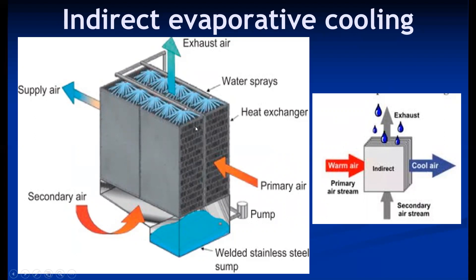In indirect evaporative cooling, since there is no direct contact between primary air and water, no absolute moisture is added to the air — only sensible cooling occurs. If the sprayed water temperature is below the dew point temperature of entering air, dehumidification is also possible, but in most cases only sensible cooling happens. This system is used where only cooling is required. Two fluid streams are used: a secondary airstream and a primary airstream.